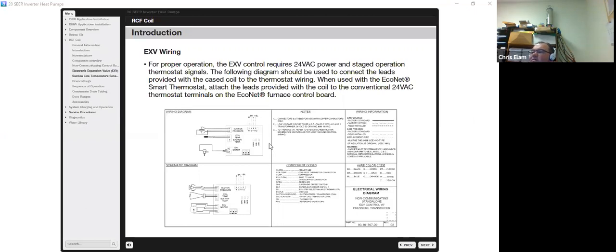This is a little bit different than the additional wiring. This is used if you're using a gas furnace with the inverter outdoor unit. So for proper operation, the EXV control requires 24-volt power and staged operation signals. This following diagram should be used to connect the leads provided with the cased coil to the thermostat wiring used with an EcoNet Smart thermostat.